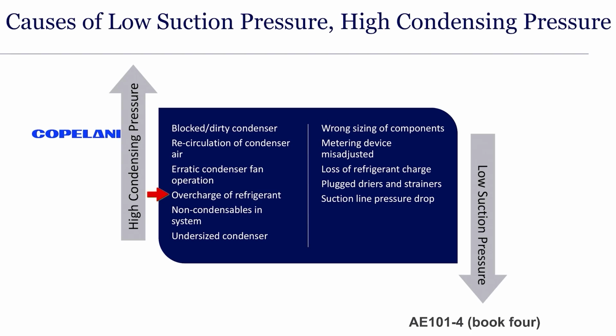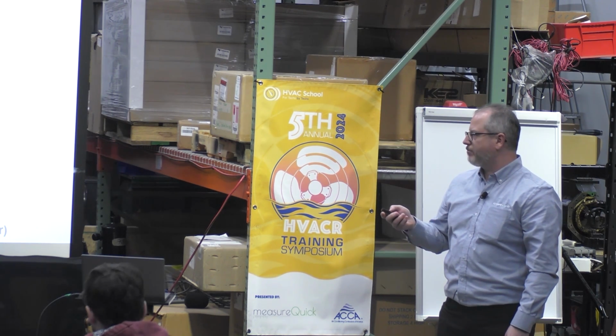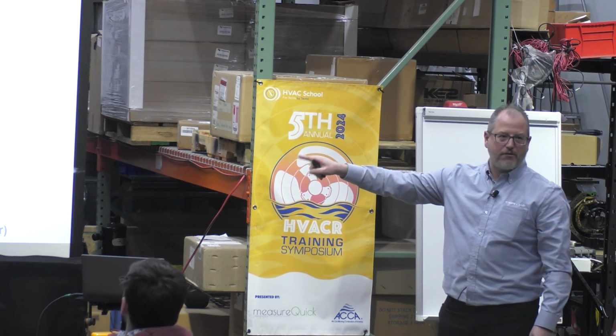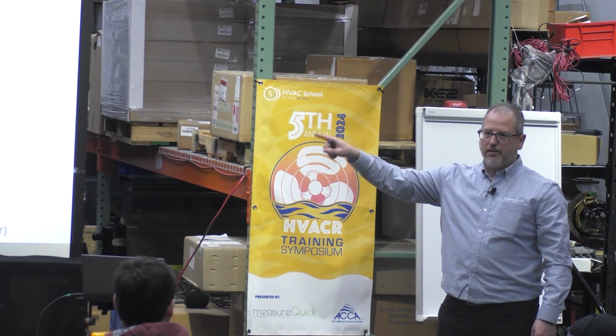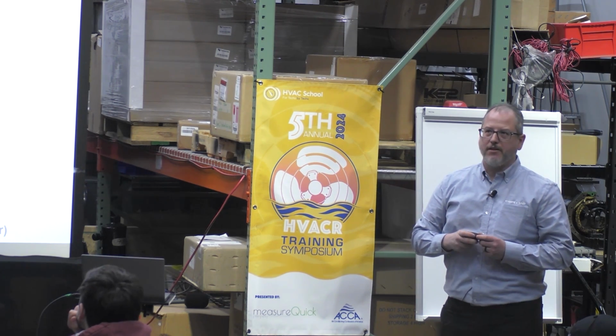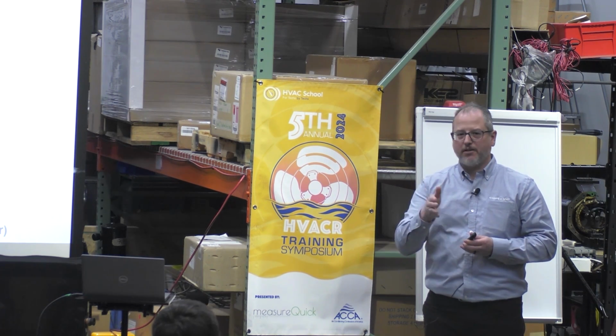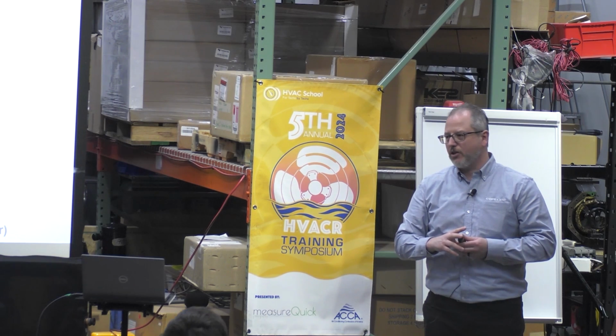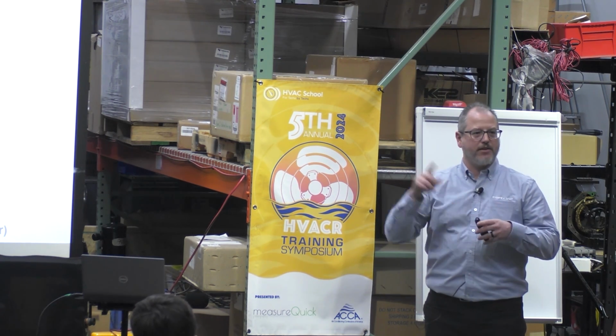If the system's overcharged, or we have non-condensables in the system, then we get to the low side. If we have the wrong components, metering device issues, that could cause a problem, right? Loss of refrigerant. So if we're low on refrigerant, plugged filter dryers and strainers in our system. So we have to be looking out for all this stuff. Suction line pressure drop. All different things that will cause low suction pressure. And again, the lower the suction pressure, that's going to affect our compression ratio more than the higher discharge pressure. Okay? So if we just talk air conditioning for a sec, if somebody has a plugged filter and their temperature is lower in their evaporator, that's going to cost them more money than if their condenser was plugged up.